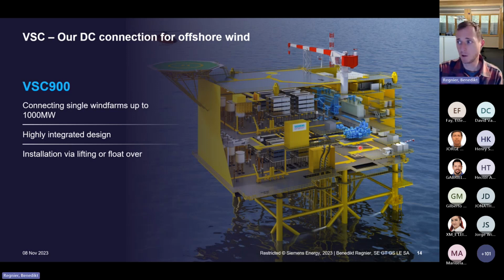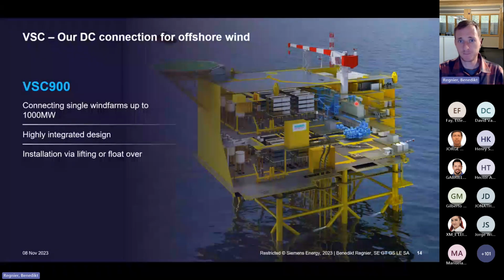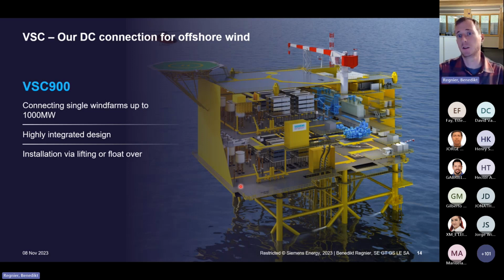We have the converters here, also indoor, and the DC reactors, the transformers. We have 2 times 100% transformers because here it's not very easy to change a transformer. That's why we have this included. The good thing for cooling offshore is that we have plenty of cooling liquid available. Namely, it's the seawater. So we can use the seawater to cool the transformers and the converters. Of course, with more than one circuit, so we're not pushing seawater through our converters. But with heat exchangers we can take out the heat, realizing these very compact solutions for offshore wind connections.